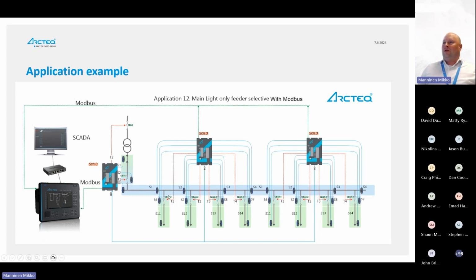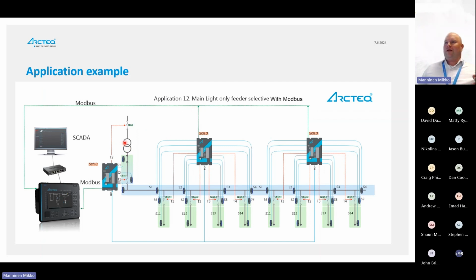Another application example here. So this is an arc protection. This is called feeder selective protection. Again, different protection philosophies. Feeder selective means that if we have a cable fault, for example, this feeder here, we only trip this breaker. And if the arc flash is here on the breaker or in the bus bar, then the trip goes to the upstream. And of course, that can be sent to other relays, for example, single line diagrams on the relay itself, and communicated up to the higher systems, for example, SCADA systems or any automation system. Feeder selective.